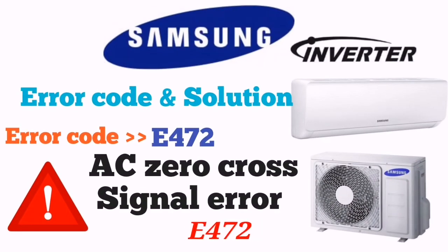When you see error E472, it means AC zero cross signal error, or LED 1 will be on, LED 2 will be on, and LED 3 will be blinking. At that time you have to restart your unit and check if the error is coming again or not. If the error is coming again, directly change the outdoor PCB and your unit will be in working condition.